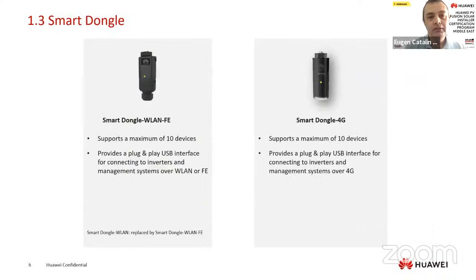For the communication, we use smart dongle in this solution. So we have two types of smart dongle: WLAN-FE that will support wireless connection or fast Ethernet connection with Ethernet cable. Using the smart dongle, we can connect in cascading scenario maximum 10 inverters, including the master. And it is a plug and play device. We will connect this device in USB port of the inverter, and the inverter will auto detect the dongle and the connection way. Smart dongle 4G, the same, supports 10 inverters in cascading scenario. It's a plug and play USB interface, yes, and so the inverter will auto detect the type of the dongle and the connection through 4G.